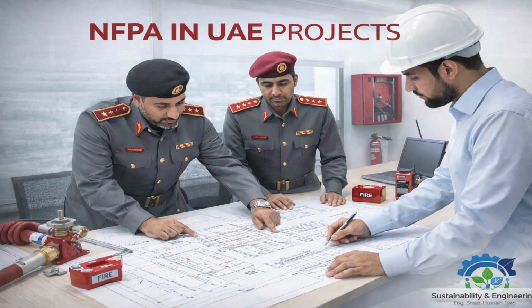This is where many engineers struggle. Common mistakes are undersized pumps, incorrect zoning, wrong hazard classification, incomplete interface with power and controls. Civil defense reviews drawings line by line against NFPA clauses. If something doesn't match, approval stops.